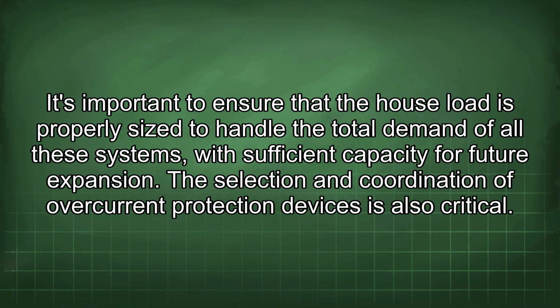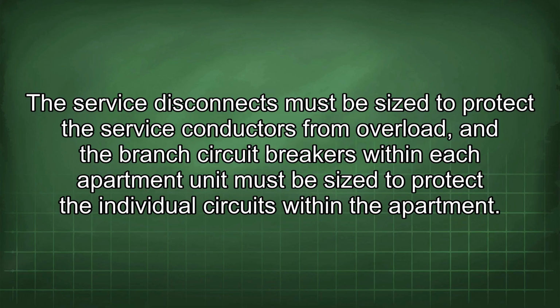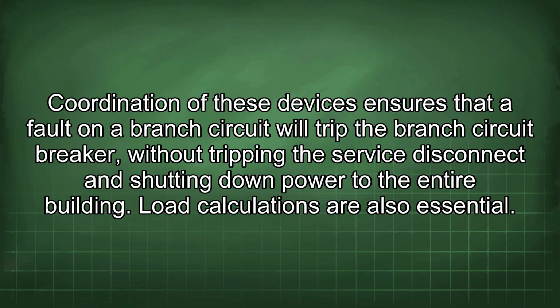It's important to ensure that the house load is properly sized to handle the total demand of all these systems, with sufficient capacity for future expansion. The selection and coordination of overcurrent protection devices is also critical. Service disconnects must be sized to protect the service conductors from overload, and the branch circuit breakers within each apartment unit must be sized to protect the individual circuits within the apartment. Coordination of these devices ensures that a fault on the branch circuit will trip the branch circuit breaker without tripping the service disconnect and shutting down power to the entire building.